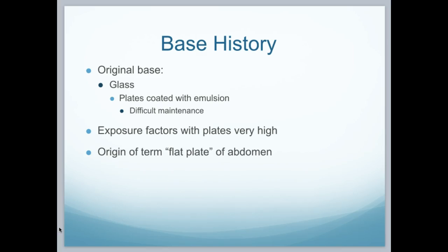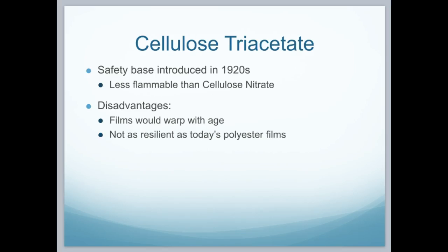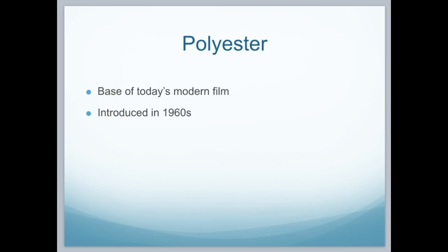There were also high exposure factors related to using this type of medium. If you ever hear the term flat plate, it usually refers to an abdomen, and that goes all the way back to this original glass flat plate. Because of a glass shortage during World War I, they quickly switched to cellulose nitrate. The problem with cellulose nitrate is it's highly flammable, and they had some devastating fires in the 20s and 30s. So they went over to cellulose triacetate, considered a safety base because it was less flammable. This all came down in the 1920s. The disadvantage was that the films would warp pretty easily. So they switched to polyester — the base of today's modern film, that light blue film, introduced in the 60s.